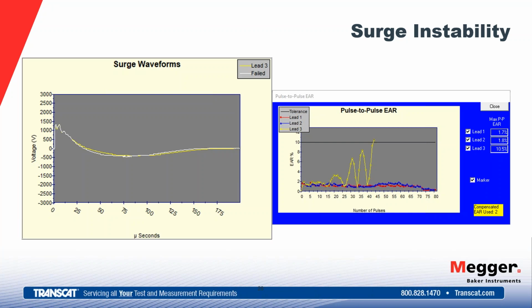And a weak turn-to-turn insulation is the beginning of the end of most insulation systems. Eighty percent, a large percentage, of failures start as turn-to-turn. So you're finding the beginning here. And as we see in this picture, this particular winding failed here as it was coming out of the slot. We can see the discoloration of the copper and the insulation there.